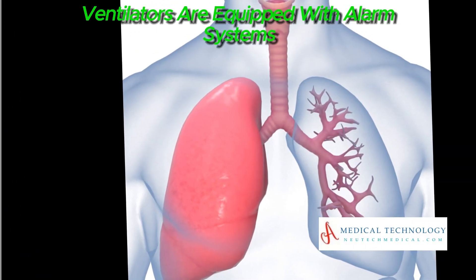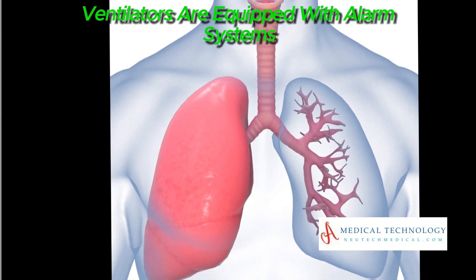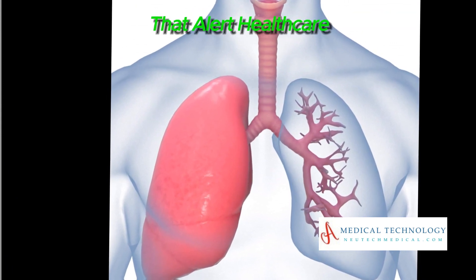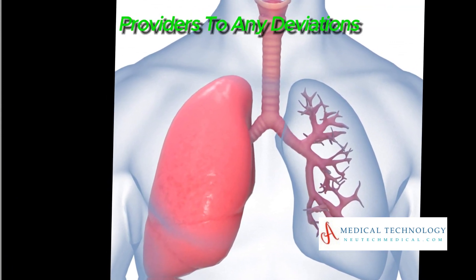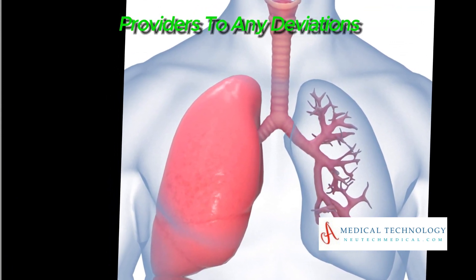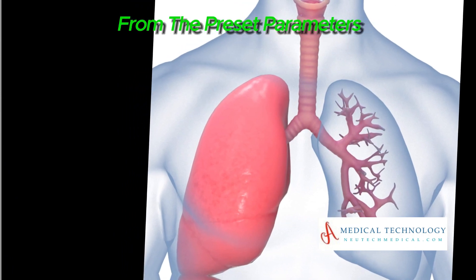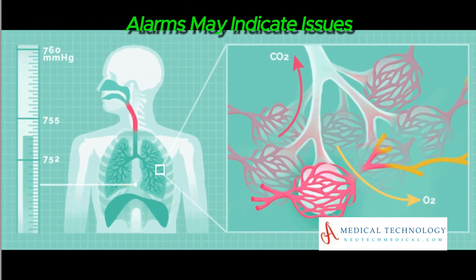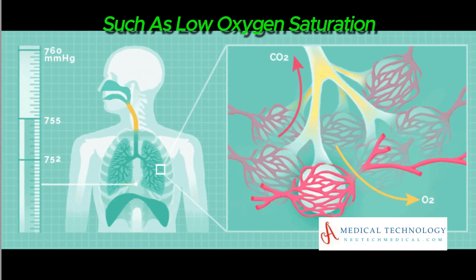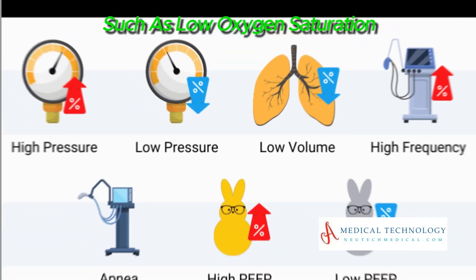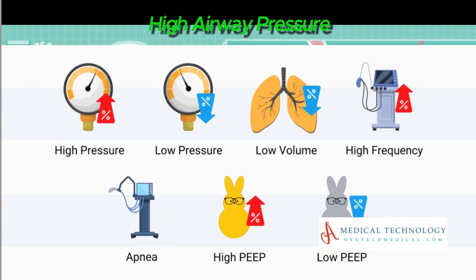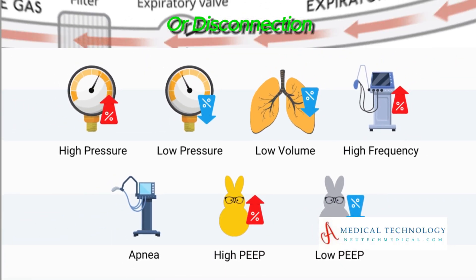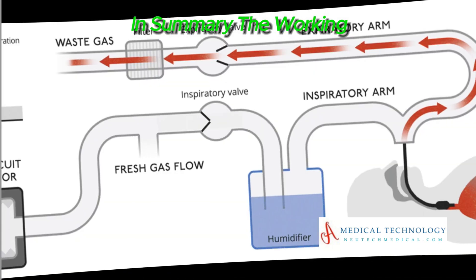Ventilators are equipped with alarm systems that alert healthcare providers to any deviations from the preset parameters. Alarms may indicate issues such as low oxygen saturation, high airway pressure, or disconnection.